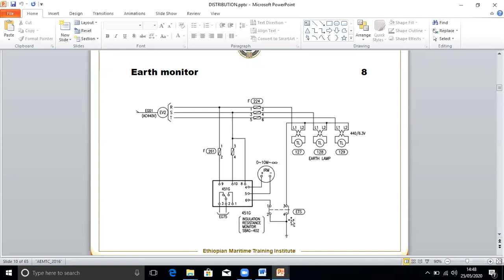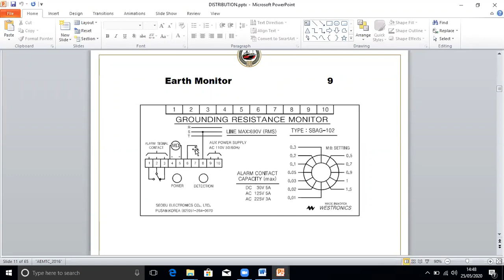This is the earth resistance monitor. On board ship, you will find a regulator like this. You can set from 0.01 to 1.5 megaohms. This is the minimum value. And you can change this rotary switch. This is basically only to stop the alarms. Whenever the insulation drops to less than, let's say, 1 megaohm, if you set it here, it will give an alarm. If you set it here, at 0.3 megaohms, it gives an alarm. Here you can see this is the alarm contact. This goes to the meter, which will show you how many megaohms it is. And this is connected from the main RST line. So this is a grounding resistance monitor.